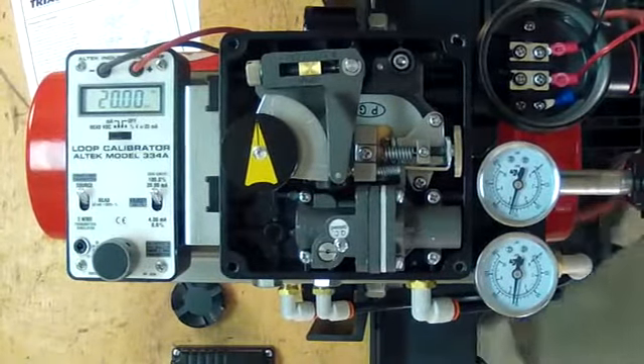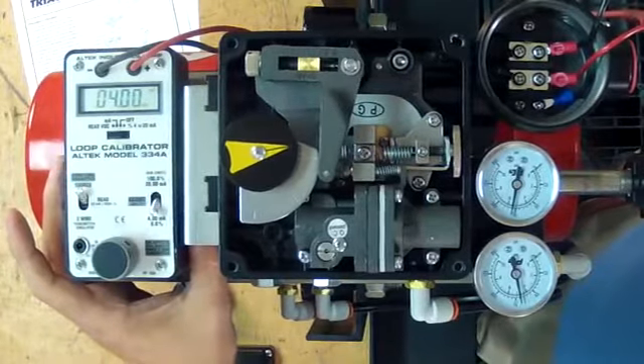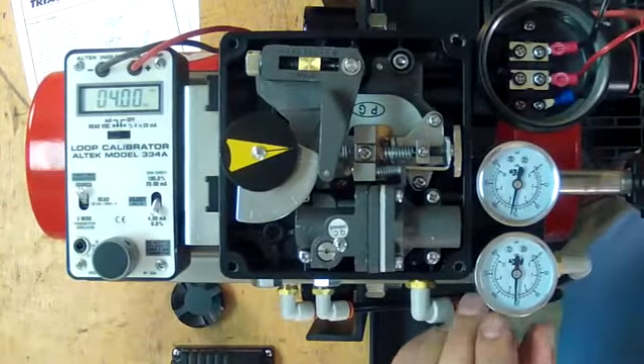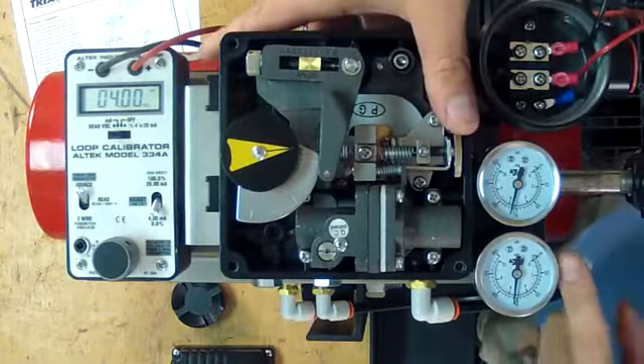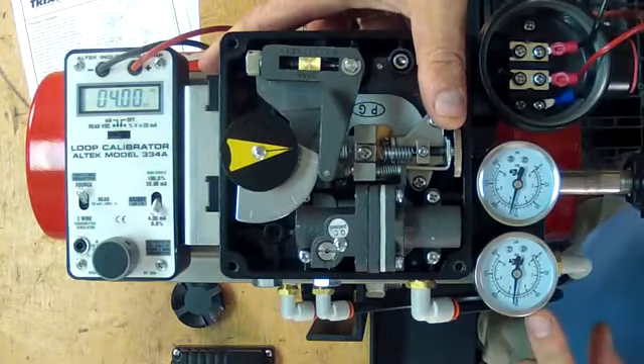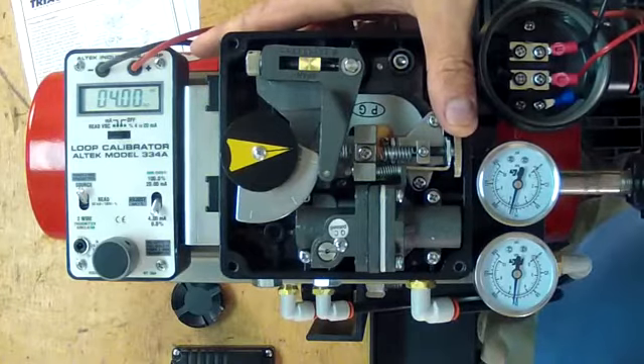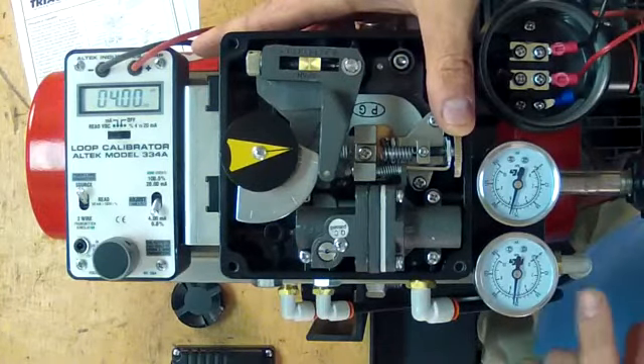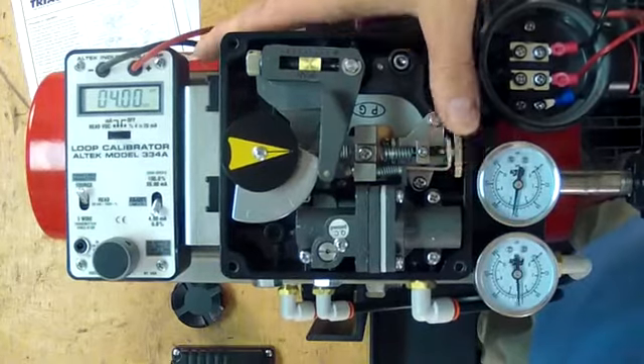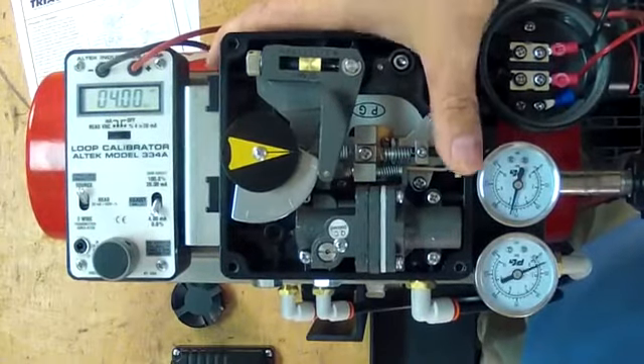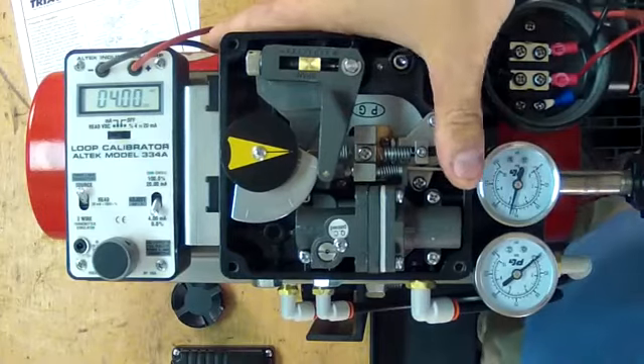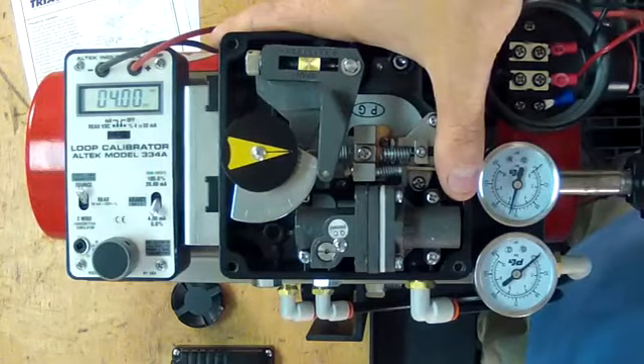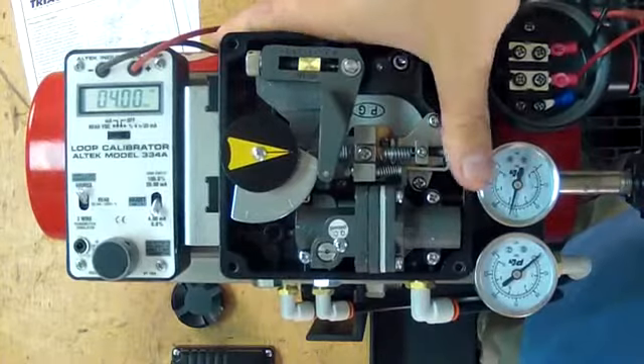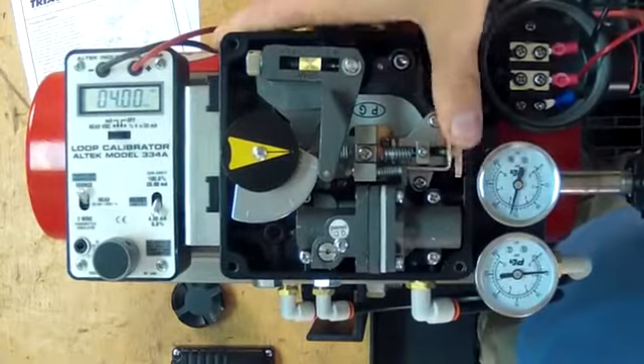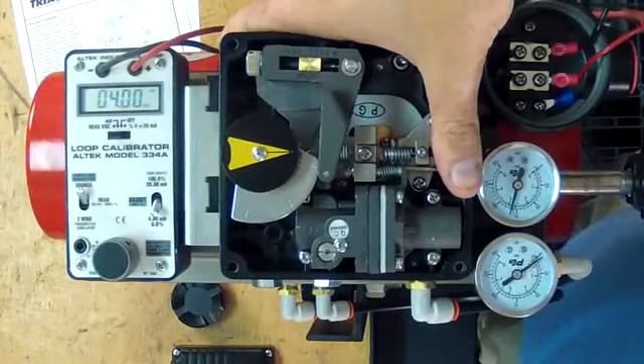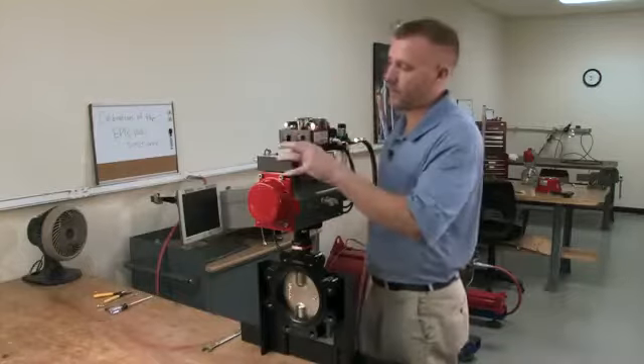Now we go back down to 4 milliamps. As you notice, there's pressure on our out 1 gauge at 4 milliamps, which you do not want. So I'm going to turn this counterclockwise till the gauge falls to 0. Now clockwise till it starts to climb, and then back it off. You're just fine tuning, basically. Okay, back to 20 milliamps now.